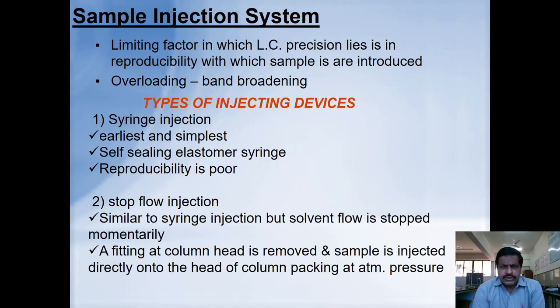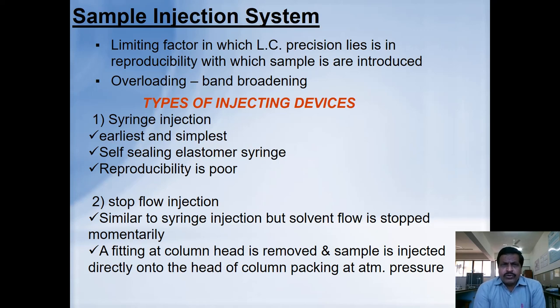The next component is the sample injection system. One limiting factor in liquid chromatography is the reproducibility with which samples are introduced. A troubleshooting issue is overloading, which occurs when a sample is injected before the previous sample has eluted, causing sample accumulation in the column and band broadening. Different types of injection devices include syringe injection, which is the earliest and simplest technique, though reproducibility is poor.